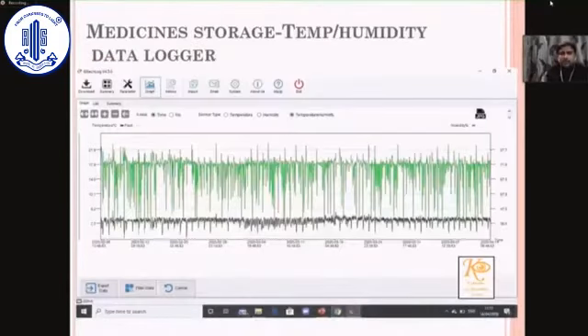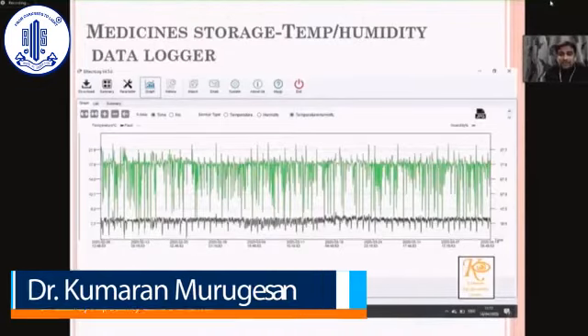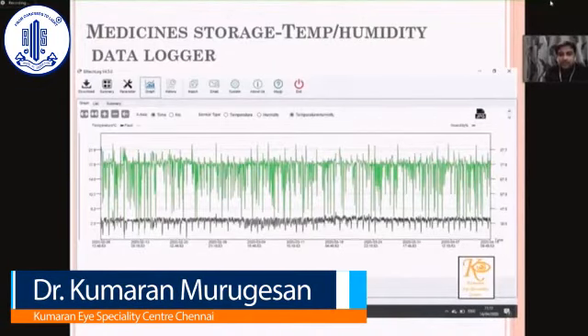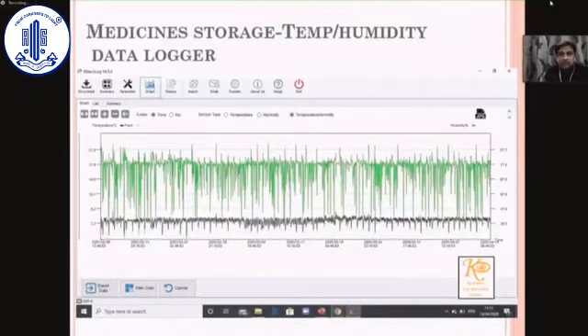So this is the data logger of my refrigerator that records the temperature and humidity every 1 hour. The logging time can be regulated from the software from an interval of 1 minute onwards. The data can be downloaded onto your system every week or as listed by your protocol in your SOP. The spikes in the graph are shown due to the change in temperature when you remove the data logger and log in onto your system.